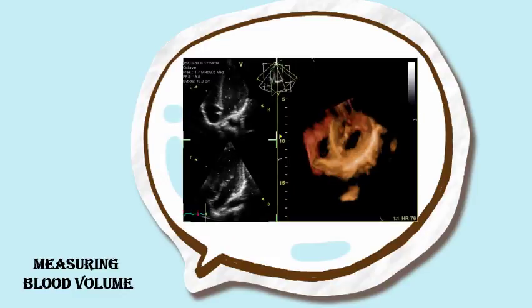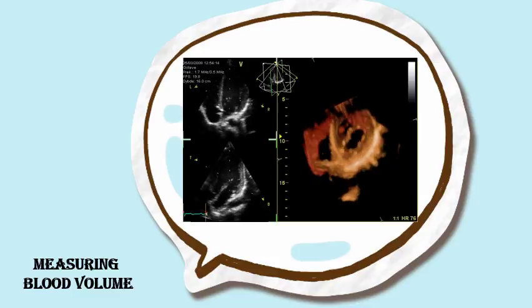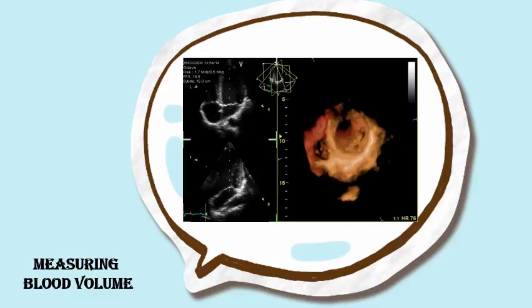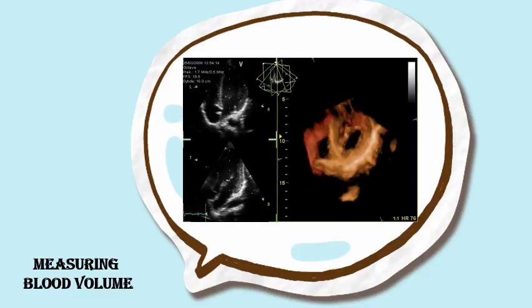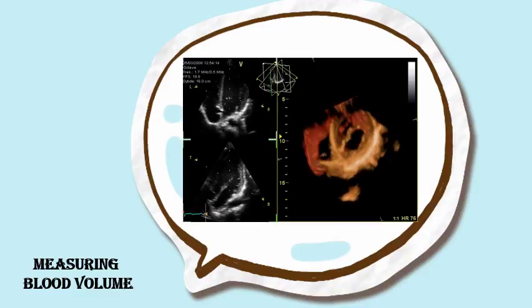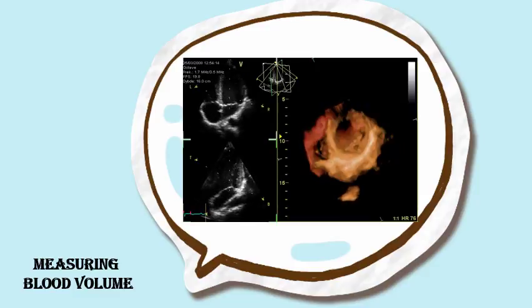4D ultrasound could also be applied in measuring blood volume and thus performing heart examination. It can make a significant contribution to our understanding of the developing fetal heart in both normal and abnormal cases. Following acquisition, the ultrasound system applies mathematical methods to process the volume data and detect systolic peaks, which are used to calculate the fetal heart rate.